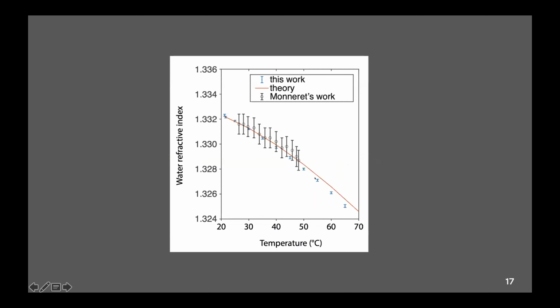What we did with the VAHEAT stage are the blue crosses, blue dots, with the error bars, compared with what was done with the heating chambers we have on the microscope. First, it's more precise, partly because we use the VAHEAT stage, but also because we improved the post-processing of the results. Also importantly, we could go much further in temperature. With the stage that was heating the microscope, we could not heat more than 40 something. With VAHEAT, we have no limit on the temperature range. I mean, we can go very far. And also it was very fast. It was like half an hour to get these measurements, compared with a full day when we were heating the microscope.